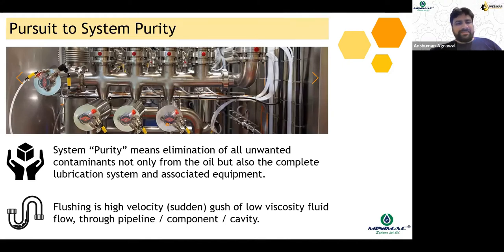Flushing is basically a sudden gush or high velocity flow of the lubricant through the system components. This is required to be done through all components, whether pipelines, valves, pumps, or heat exchangers. Any cavity or internal of your entire system needs flushing.